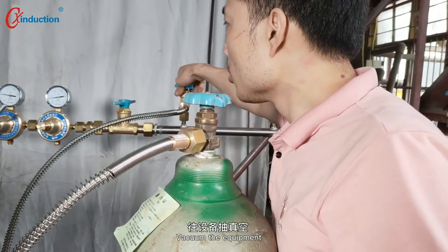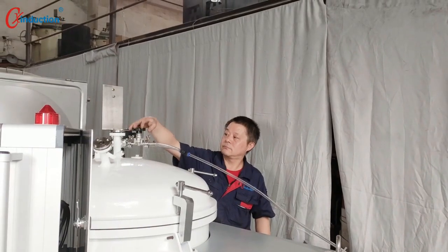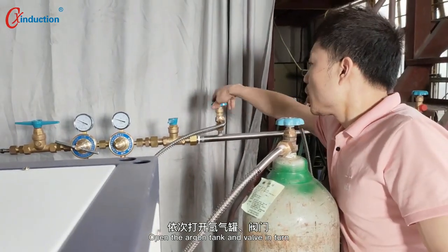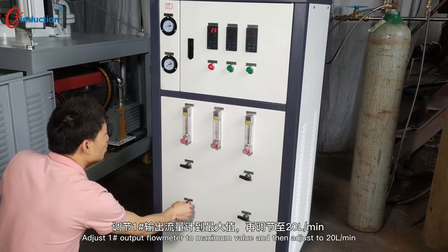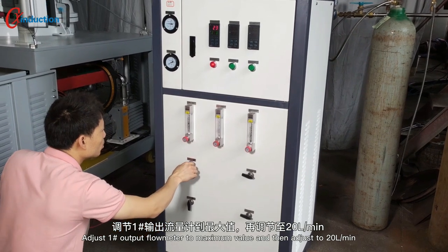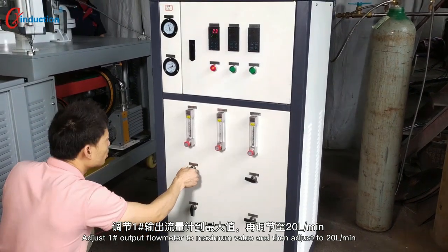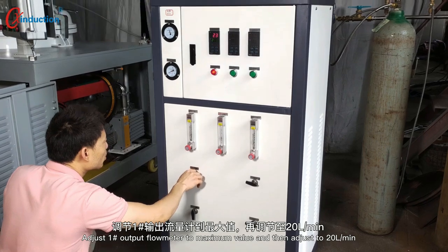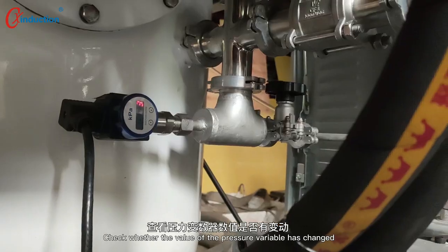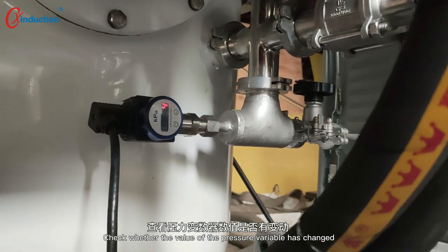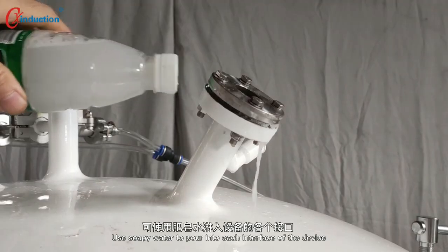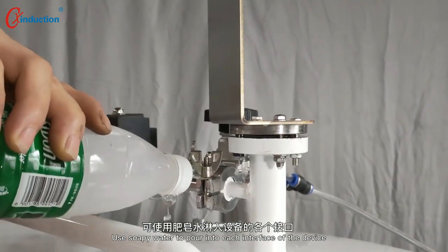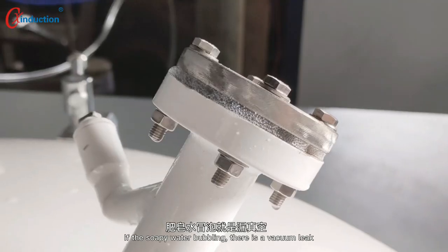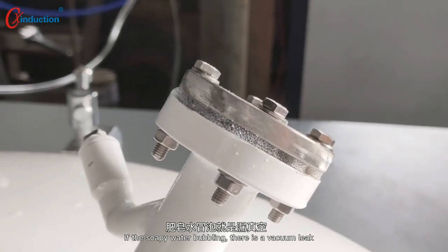Vacuum the equipment. Open the argon tank and the valve in turn. Adjust number 1 output to the maximum value and then adjust to 20 liters per minute. Check whether the value of the pressure variable has changed. Use soapy water to pour onto each interface of the device. If the soapy water bubbles, there is a vacuum leak.